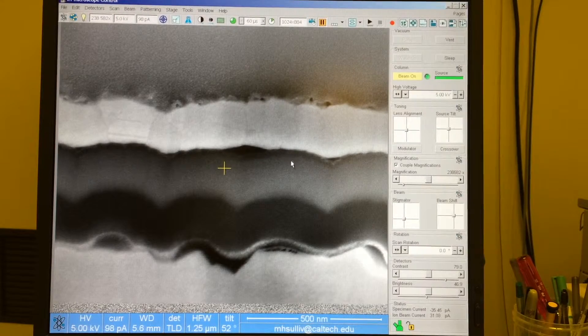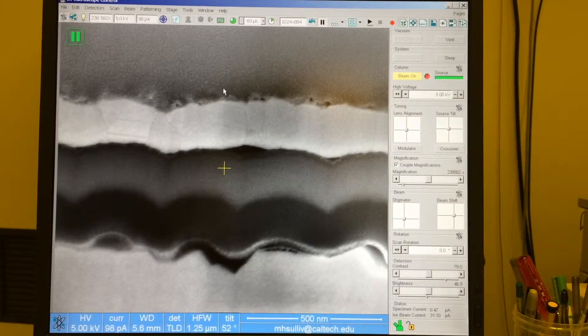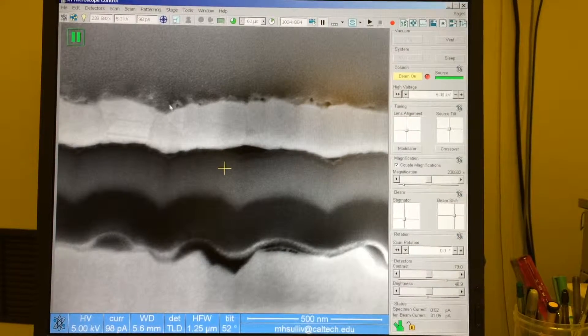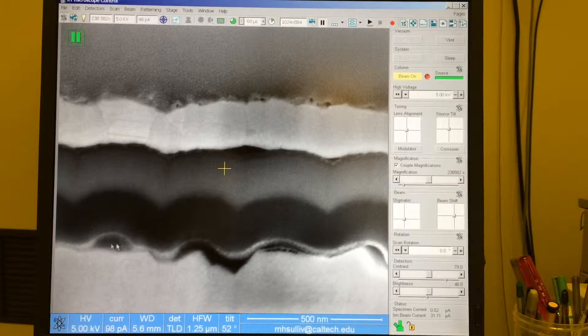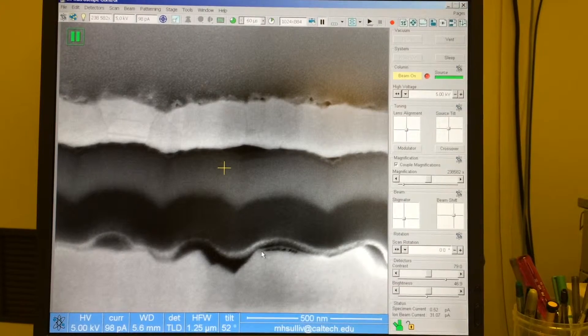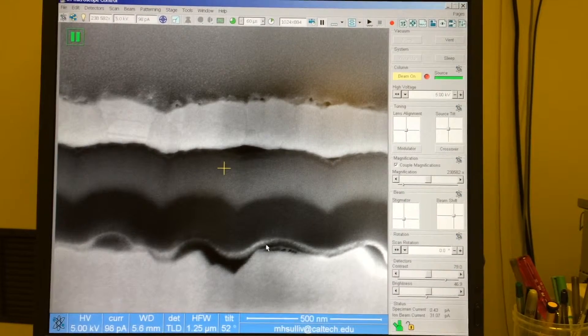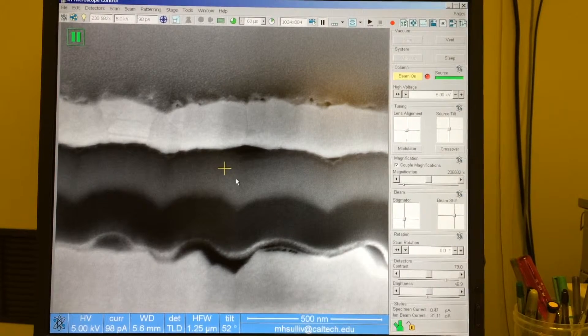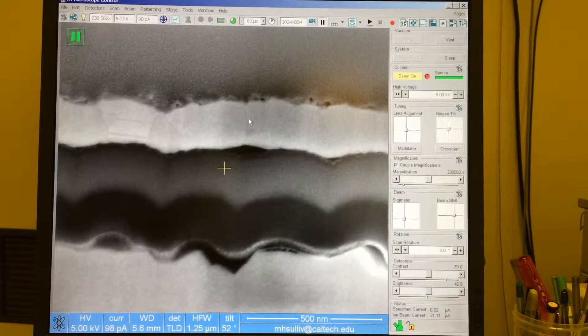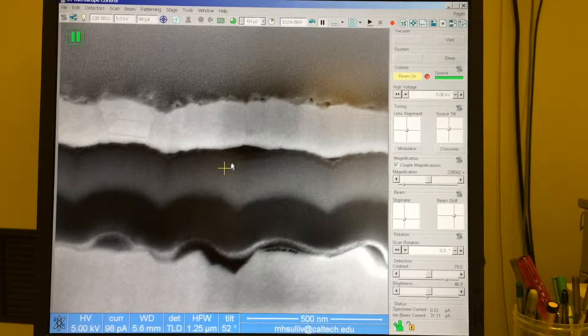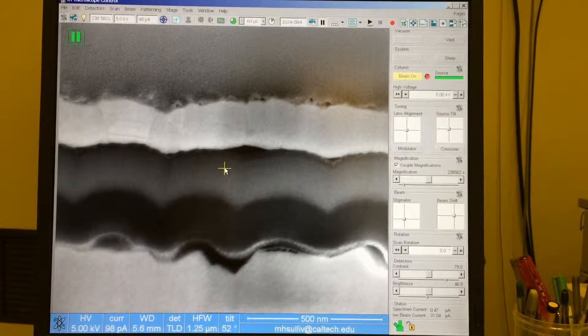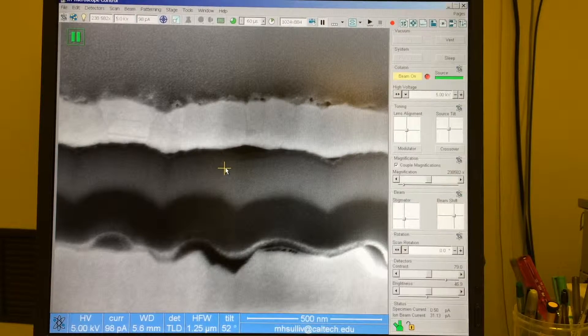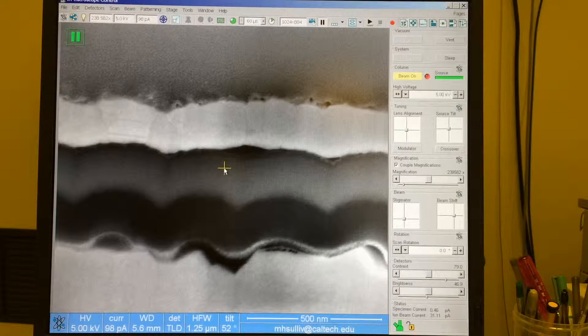Now, one thing we notice here, there are a couple of artifacts we want to be aware of. At the top of the image, we can tell that we have really excellent focus and astigmatism based on that nano-texture. If we look down here at one of these bottom layers, we can tell that it's a little bit out of focus, and also probably a little bit of astigmatism based on the way that it's slightly stretched. And the reason for that is when we're in immersion mode, we have a floating lens between the pole piece and our sample surface. That minimizes the effective working distance, which gives us a really steep convergence angle on the beam, and that makes us have very small depth of field.